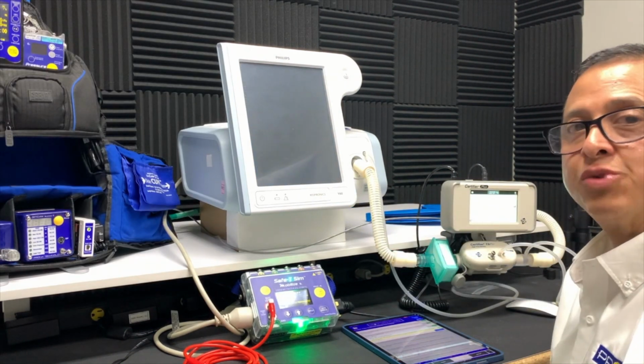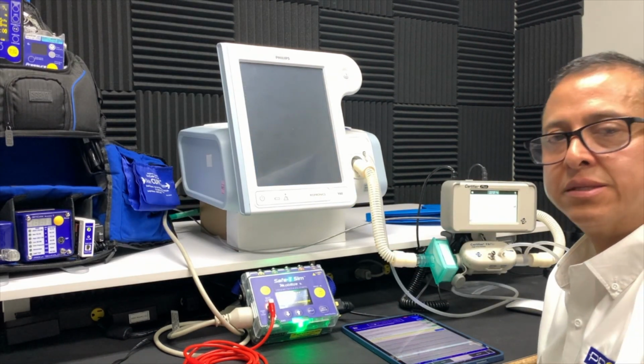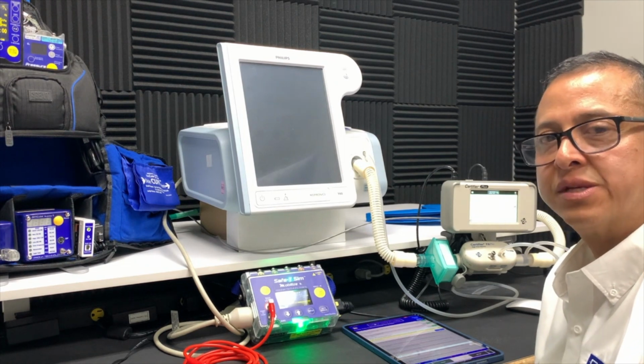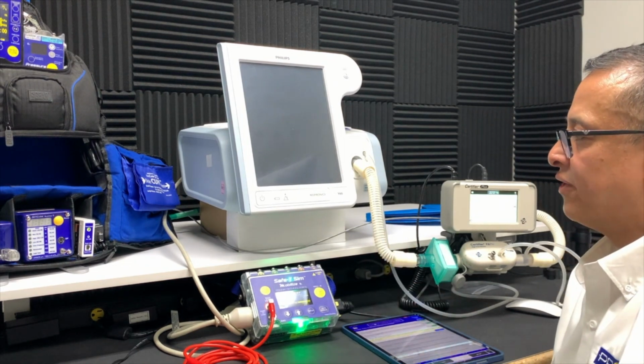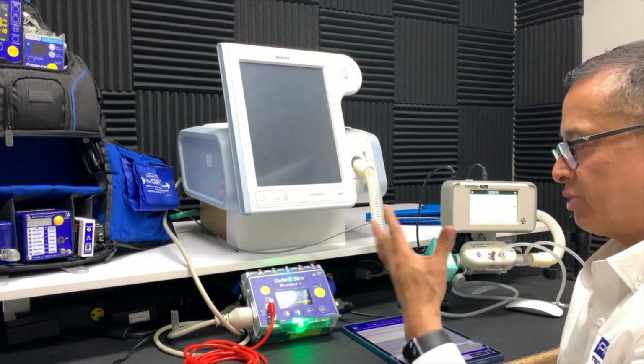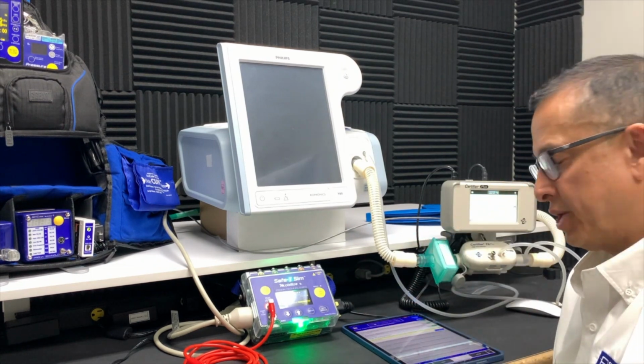So the next set of tests we need to perform are the ST performance tests, or the spontaneous trigger test, verifying various modes of the ventilator that it's functioning properly when it's programmed to deliver ventilation to the patient.